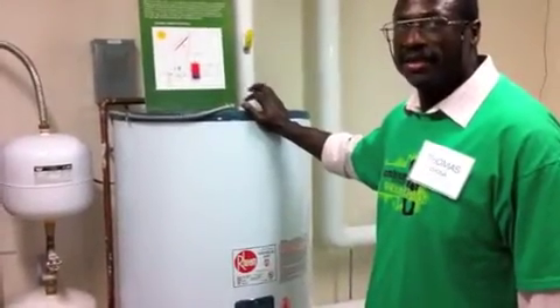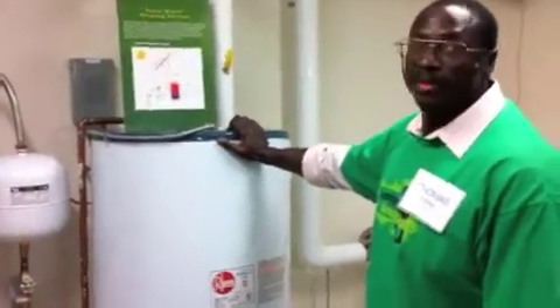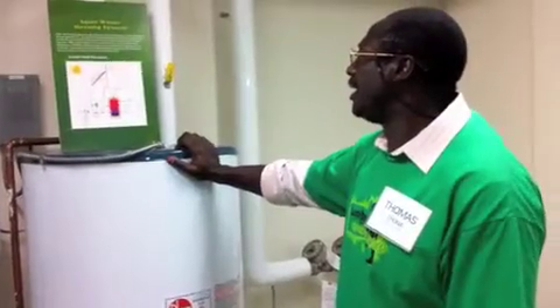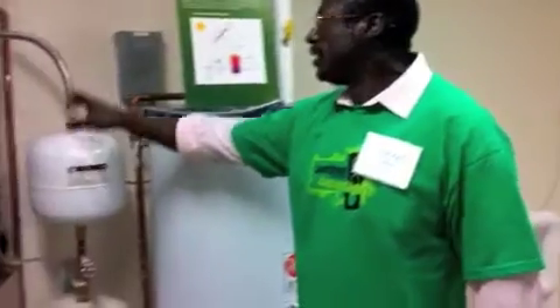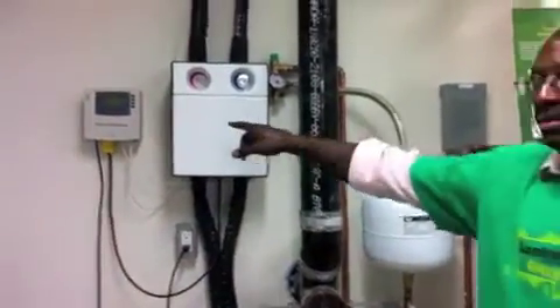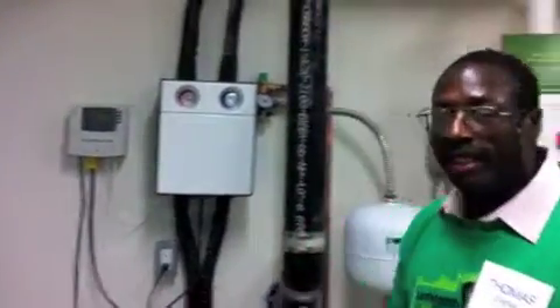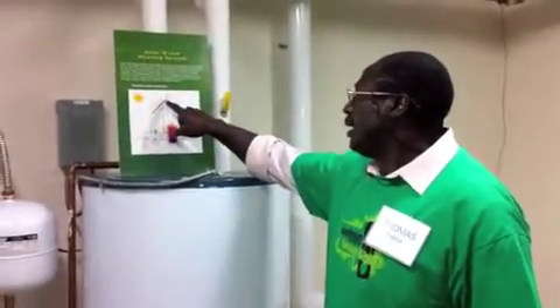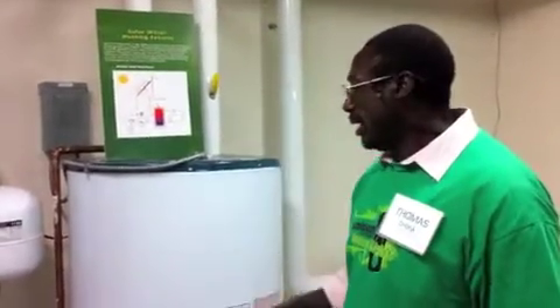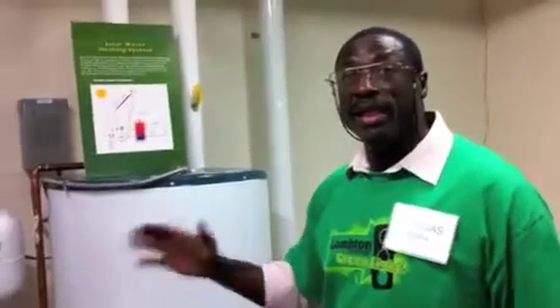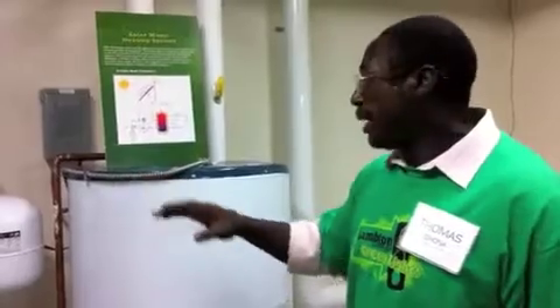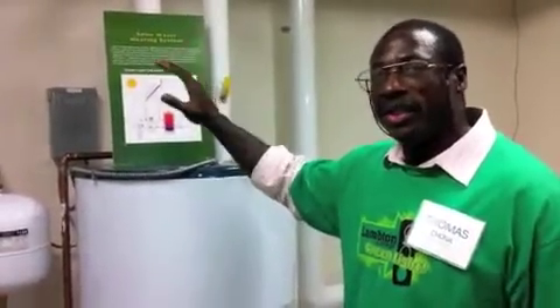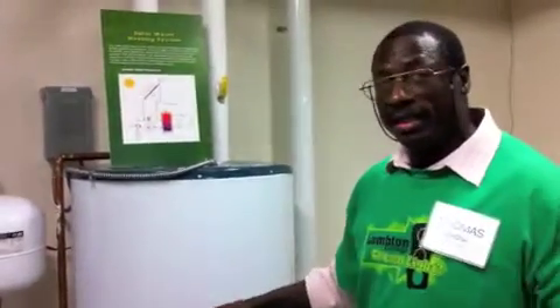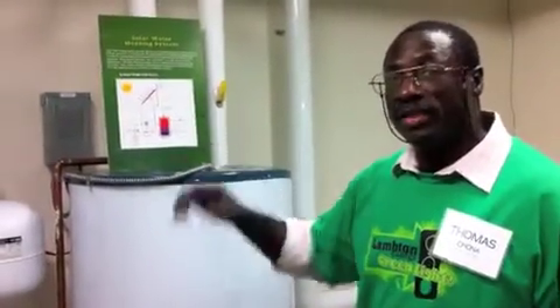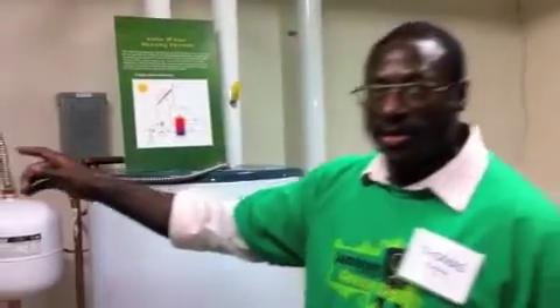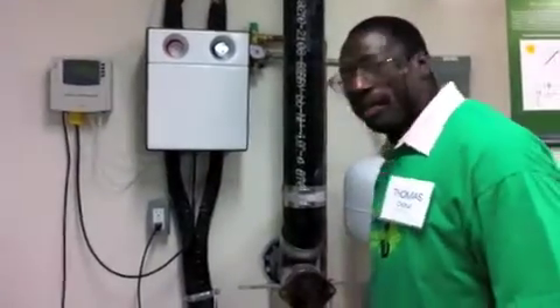Then we have the tank, which is here. And the third part, or it's actually a group of parts, we call the liquid handling unit. That's the pipes you see here, all these safety devices, and the pump. The brain of the system is here, which is the solar controller. It has a sensor at the top of the solar collector and a sensor in the tank. So what happens is in the evening when it's cold, the system is not running because the fluid in the collector is colder than the water in the tank. So when the sun comes up and there's a 5-degree difference between the water in the tank and the collector, the pump comes on. So there's a pump in here and it runs on glycol.